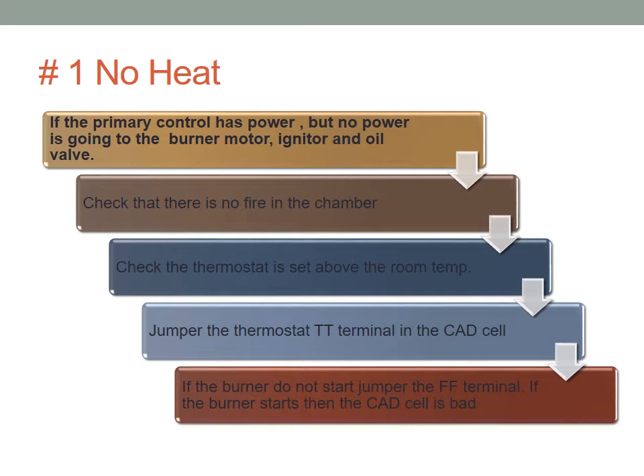Again, if the primary control has power, but no power is going to the burner motor, ignition coil and oil valve, what could be the problem? First of all, check that there's no fire in the chamber. We check that everything is getting power, but there's no fire. If there's fire, what would happen? We've been through this a lot. We said if we have fire, it means the control is not going to ignite because it will think there's fire, and it's a bad situation to throw fire and oil into it. So make sure that there's no fire. If there's fire, find out why and what happened before. So that could be the problem.